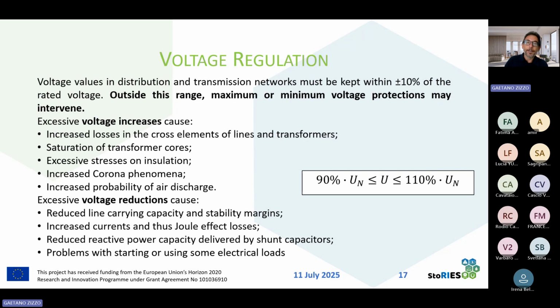reduced reactive power capacity delivery by shunt capacitors that need an adequate voltage for delivering their function in a proper way, and problems with starting or using some electrical loads, in particular some loads based on electronics. So our objective is to maintain voltage between 90% and 110% of the rated voltage of the system.